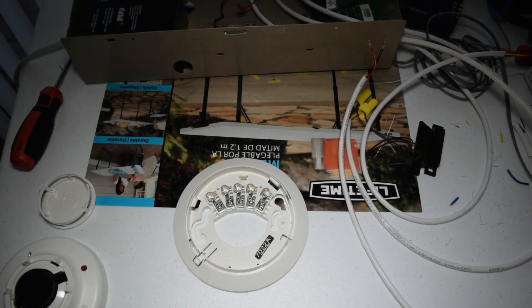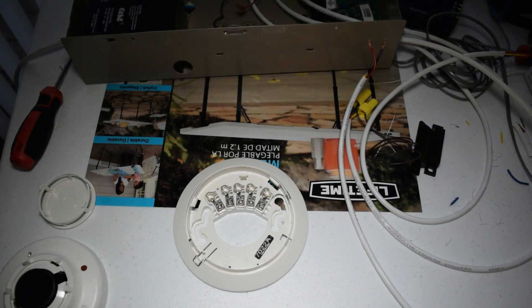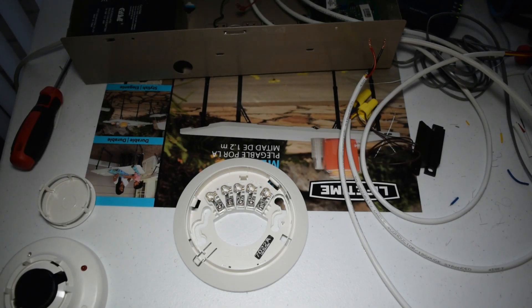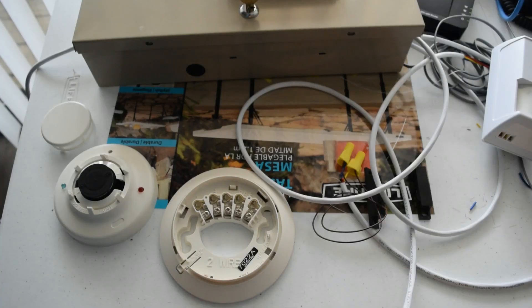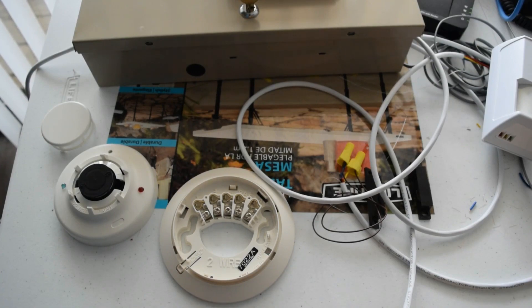And the extra positive terminal is actually reserved for bridging a resistor from the positive to the negative. So yeah, another thing about this smoke detector, or just actually regarding the two wire fire zone in general, is that it actually requires a resistor to be installed in line for it to be recognized by the panel.